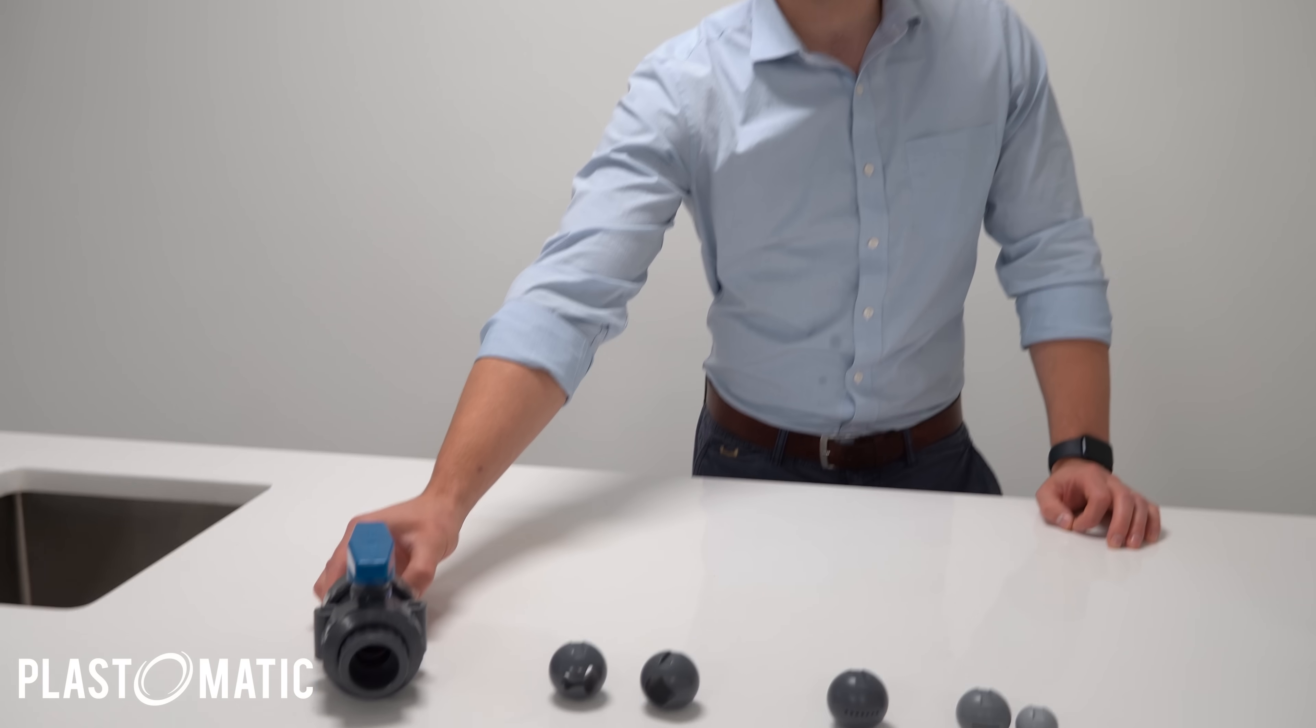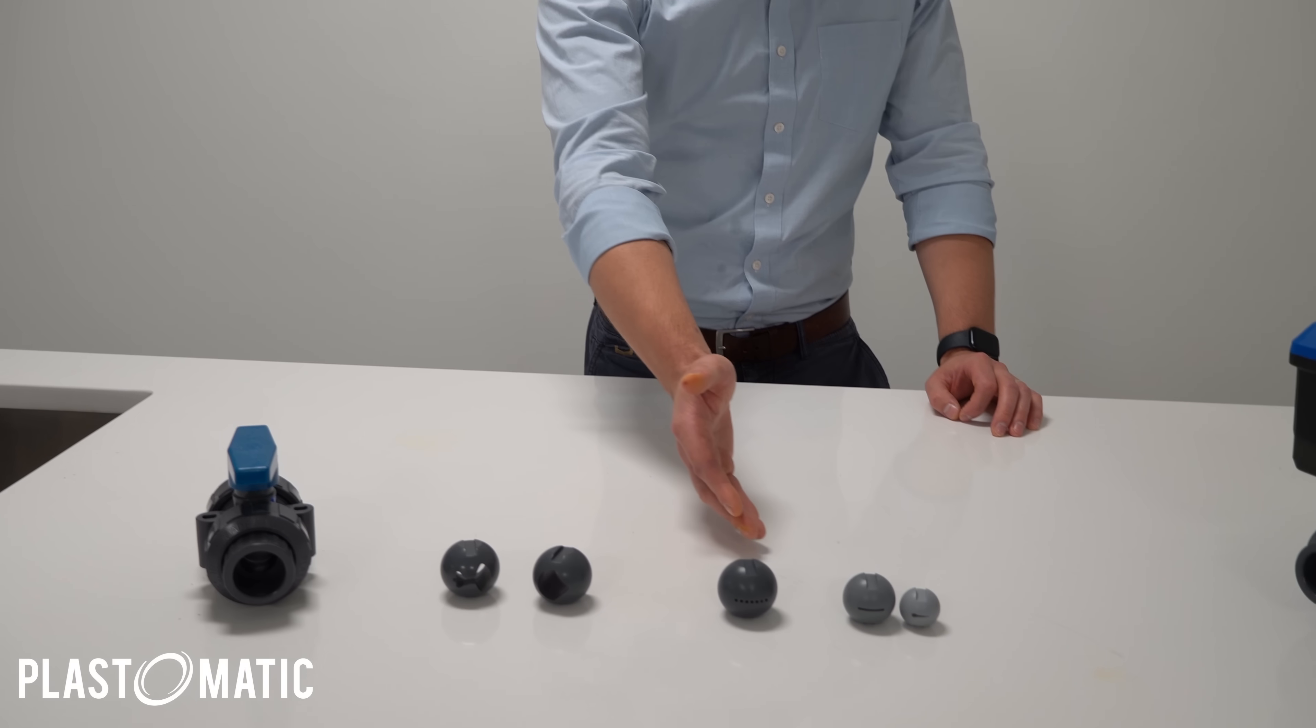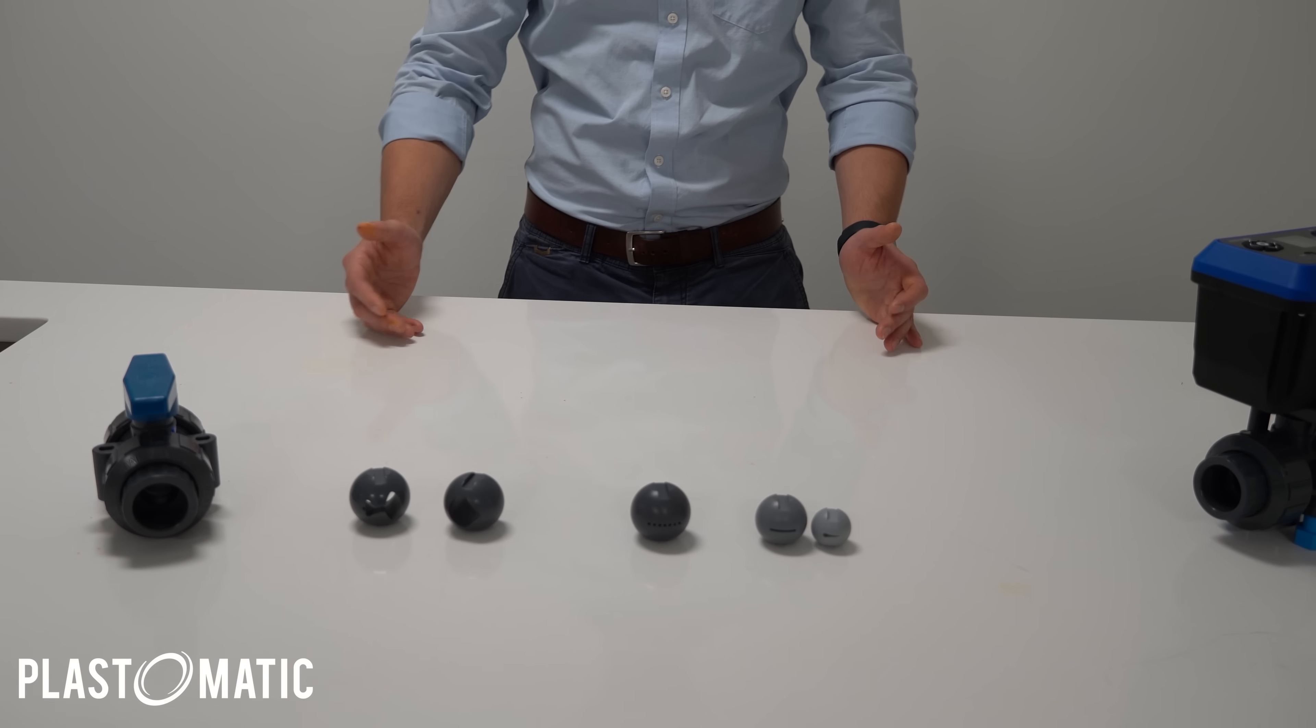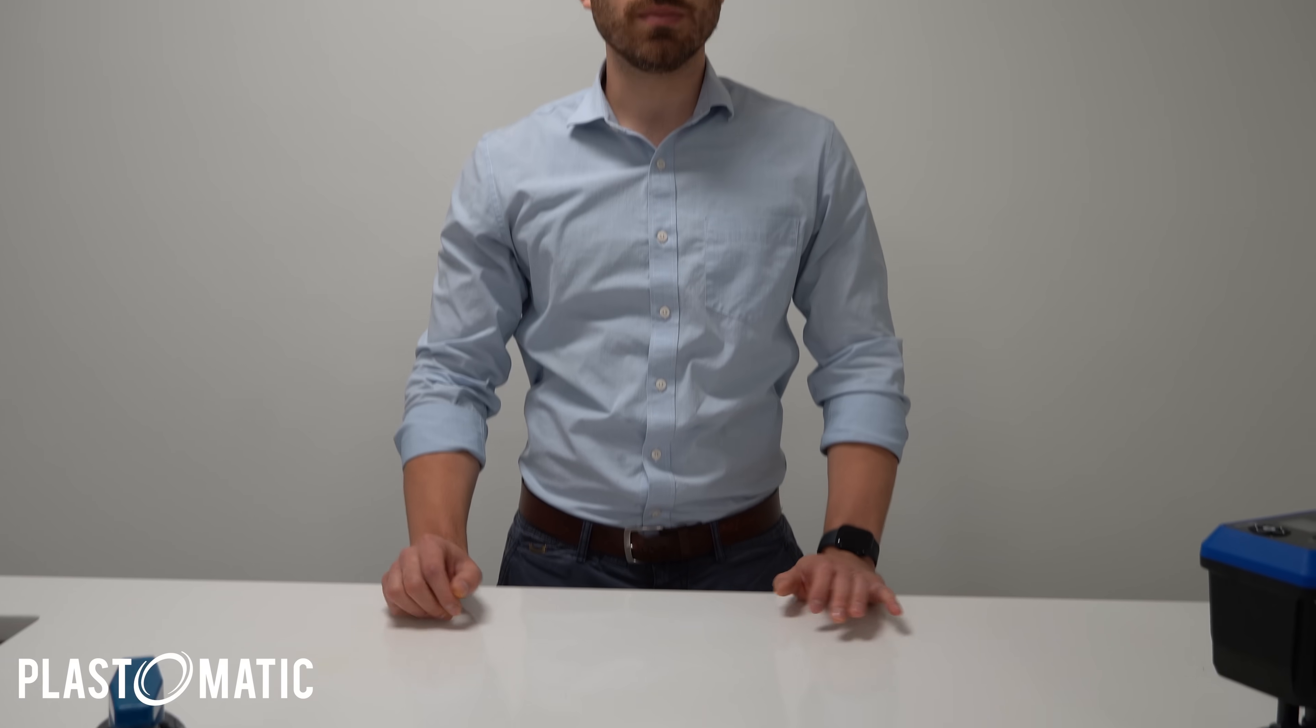You can control flow or modulate flow with a full-port ball. However, what you will find is you're going to have difficulty dialing it in to your specific requirements. So if you have a very tight tolerance on your flow demand, doing it with a full-port ball is going to be very difficult. Doing it with a characterized ball that has been tailored to your application is going to be seamless.